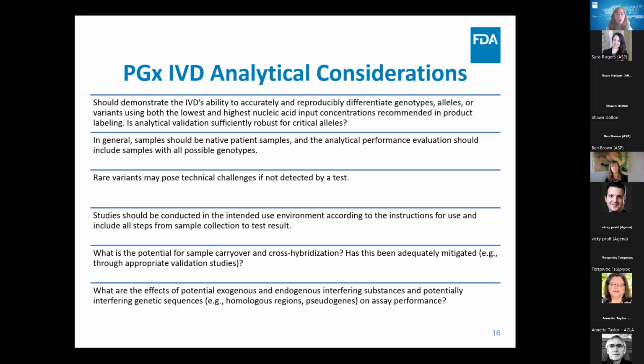Samples should generally be native samples from the intended use population whenever possible, though when fresh samples for rare alleles or genotypes are scarce, we do consider the use of archived or retrospective samples. And though natural samples are preferred, we also do consider contrived samples, especially for rare variants. We also recommend evaluation of test samples that encompass all genotypes in the test system. And studies should be conducted in the intended use environment, so again, clinical lab or point of care, according to the instructions for use, and should include all steps from sample collection to the test result.